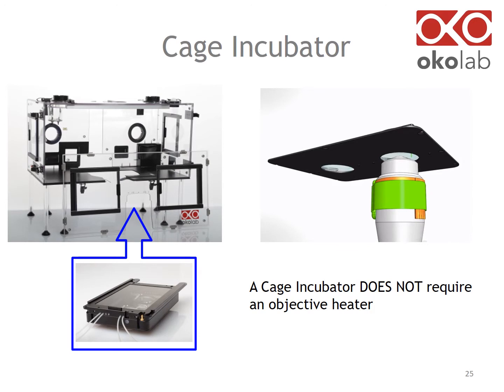When using a cage incubator, you don't need an objective heater because the objective and nose piece are inside the enclosure at 37 degrees.